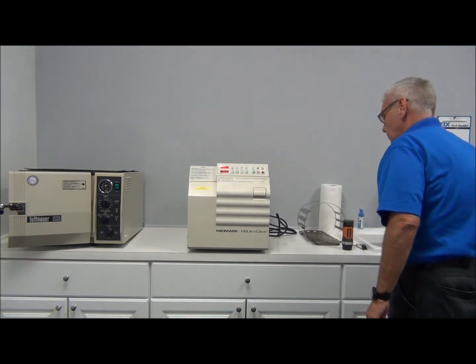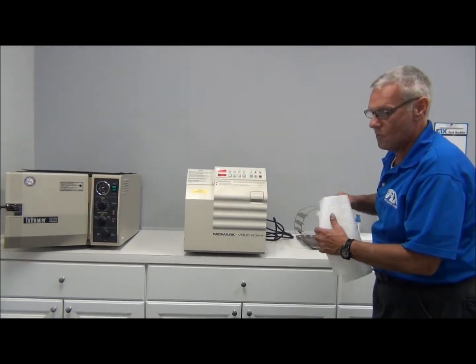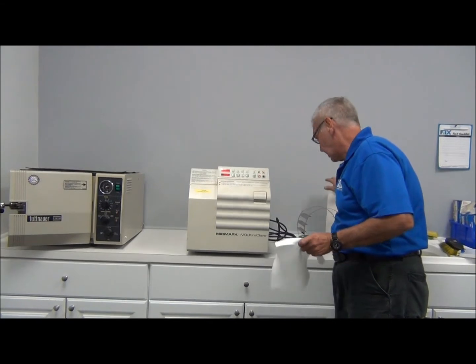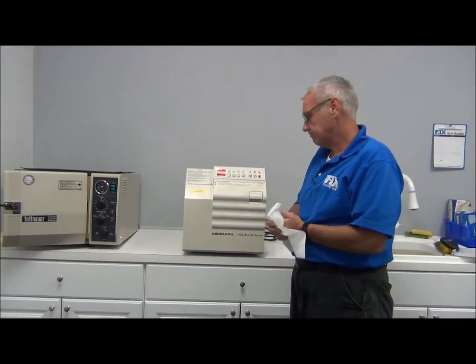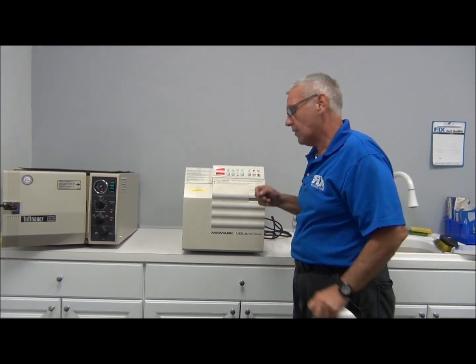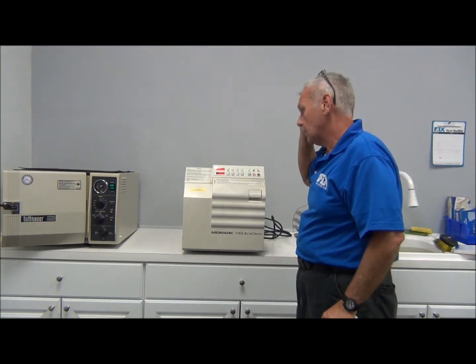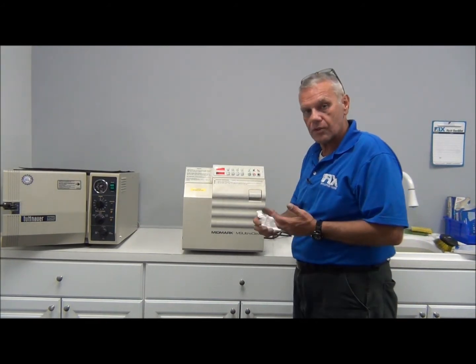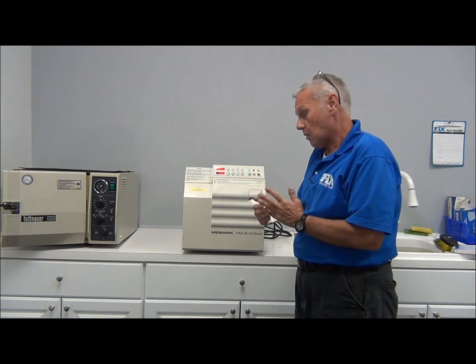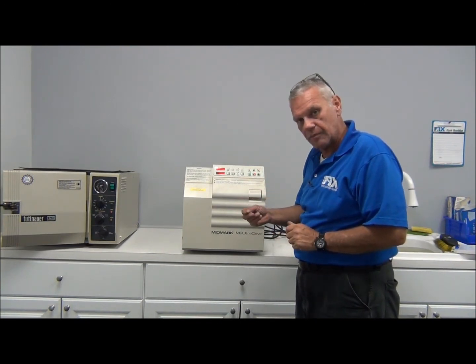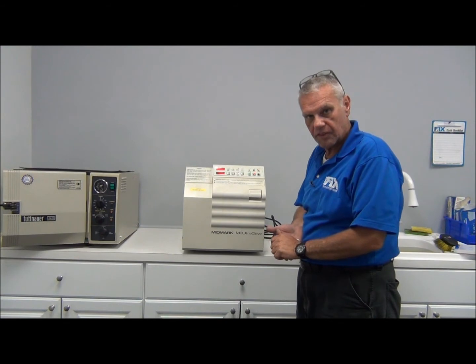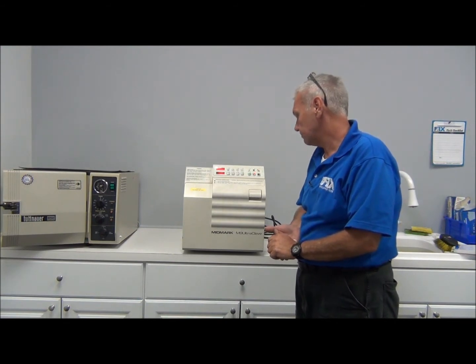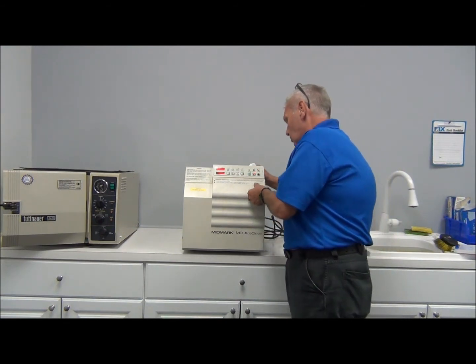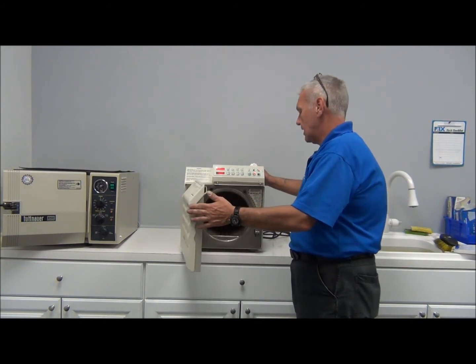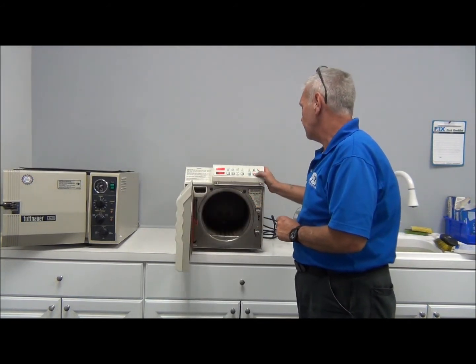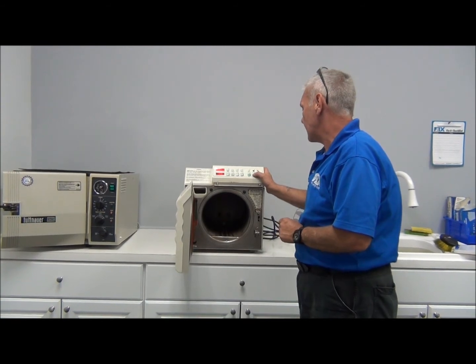It's also a good way to do preventive maintenance on the sterilizer. They're going to cost you, so for the first free preventive maintenance, you may not want to volunteer your PM kit unless you want to spend the money for it. However, the check that we're doing right now will ensure almost to 100% that the doctor will purchase the PM kit and retain you for preventive maintenance on the sterilizer in the future. Now we're going to see if the door has enough pressure on it to open, and we're fine. Let's hit stop over here, so we're not worried about the pesky beep beep.